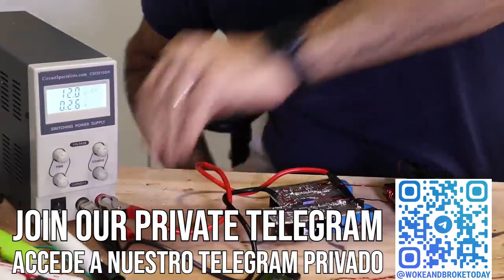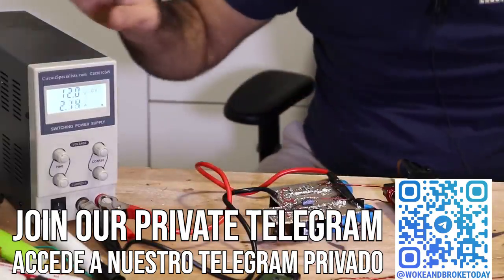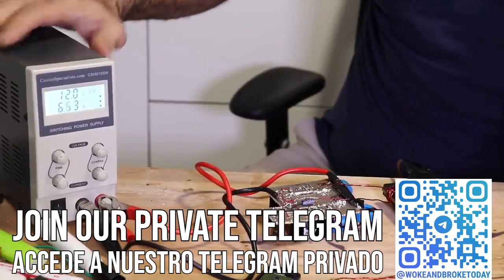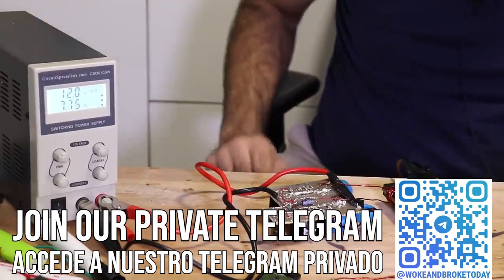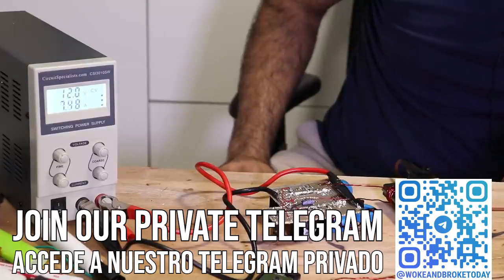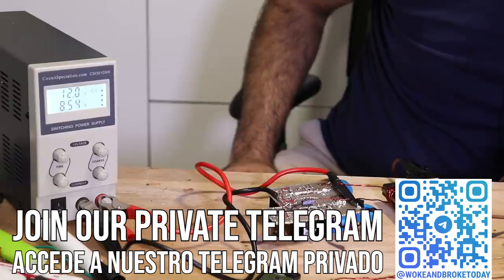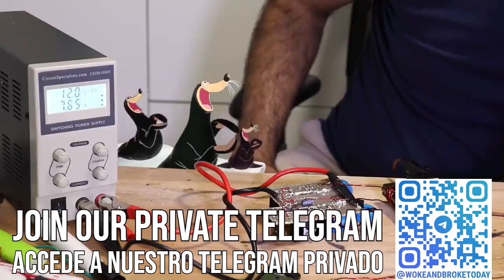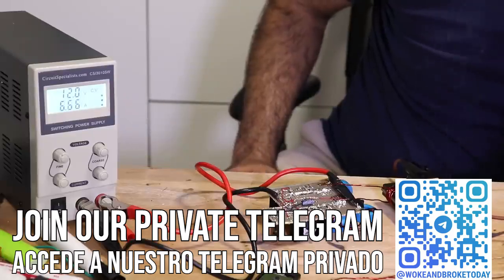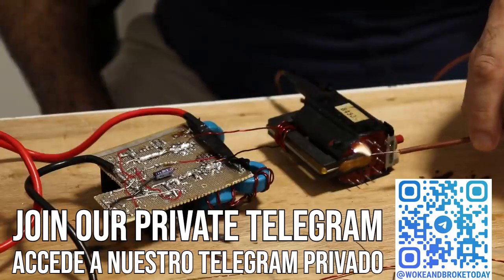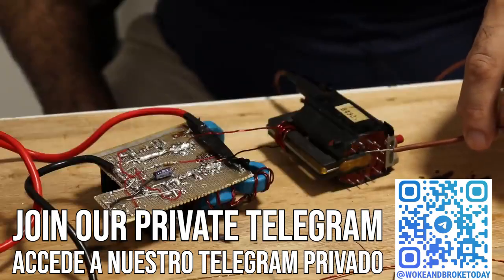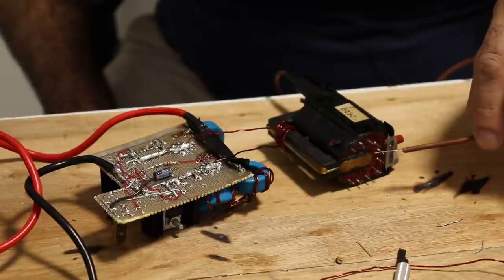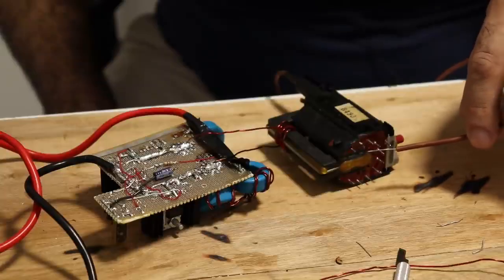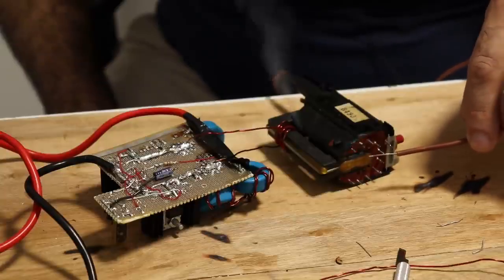Here we go. Is it on? So much current, and it's rising. Is there any arc? Oh, look at that! Interesting, when it arcs, the current goes down a little bit. Arcs! High voltage arcs! Look at these arcs—from the size of the gap, when it just starts jumping, I'd say the voltage is around 5 to 6 kilovolts.